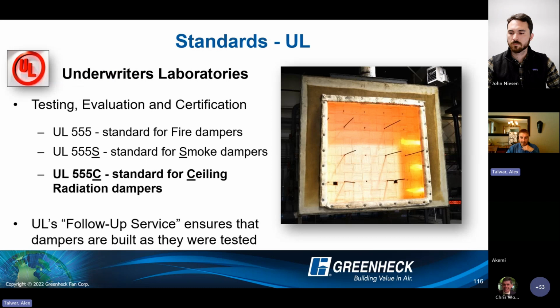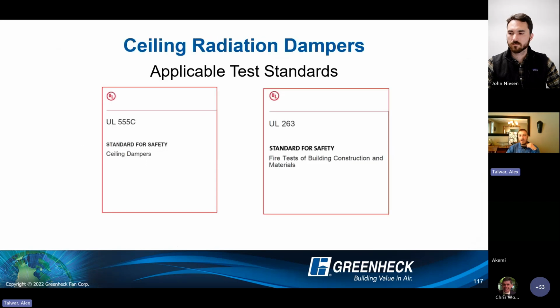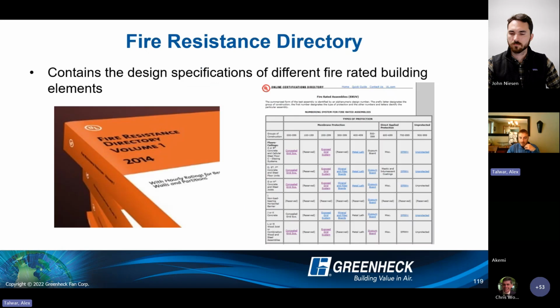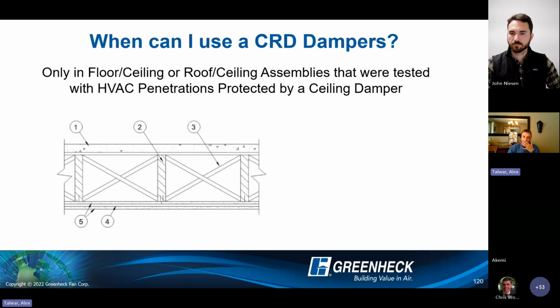Showed that slide earlier. We're talking about UL 555C now for ceiling dampers. Also talking about UL 263. So that's kind of the test standard for the floor ceiling and roof ceiling assemblies themselves. So we do start touching on that test standard as well. But ultimately, the important thing with a ceiling damper is to try to know what the ceiling design number is associated with that construction, and that will dictate what type of damper we can use here.